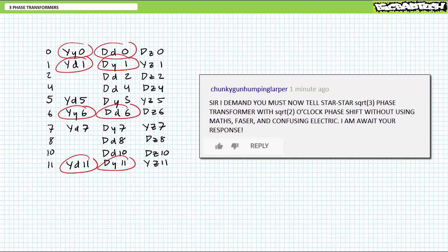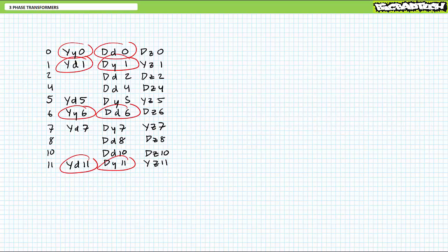But I am leaving the rest of these rarities as examples for you to work out on your own using the tools I gave you today. Really, the intended purpose of this lecture was not to slog through the transformer dungeon and slay every goblin, giant spider, gelatinous cube, and dragon in it, but rather to simply introduce transformer nomenclature, displacement diagrams, and simplified connection diagrams on an introductory level. Again, in ordinary circumstances, most of the time you'll have a simplified connection diagram on the transformer nameplate available, and it's up to you to interpret it properly and hook it up exactly as illustrated, with 0 points being awarded for creativity.